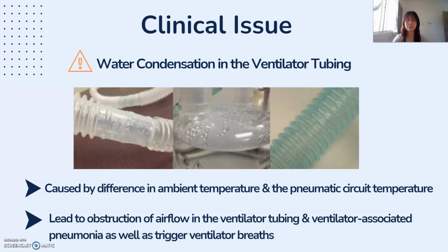Water condensation within the ventilator tubing presents a challenge to ventilator operation as it may obstruct airflow in the ventilator tubing and also triggers ventilator breath. It may also lead to ventilator-associated pneumonia as the contaminated condensate may drip into the patient's lung. In order to solve the issue of water condensation in ventilator tubing, 3 experiments are proposed.